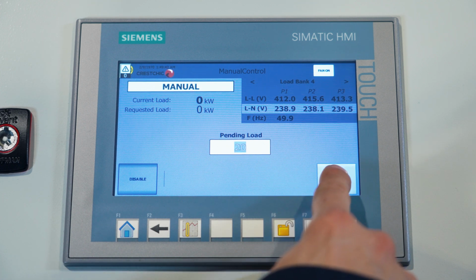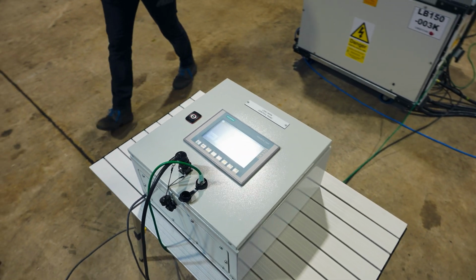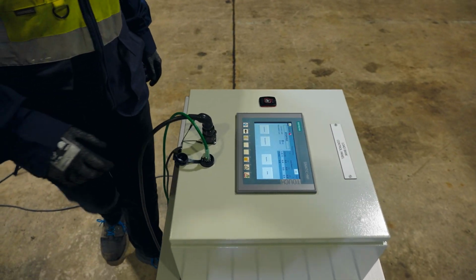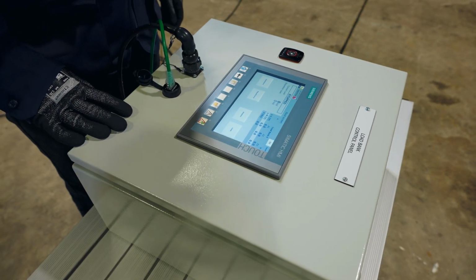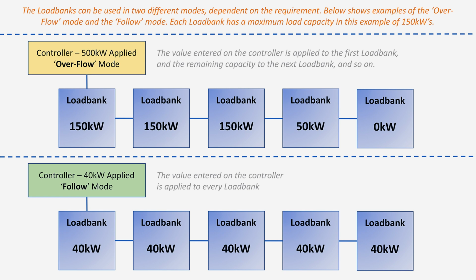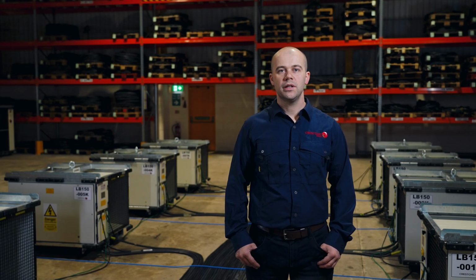Both three-phase and single-phase configurations are available for extra flexibility. The load banks can be controlled from one central controller, with instrumentation showing individual and total system load. And with two different modes available for load control operation, the load banks can either be loaded equally with the same load on each load bank, or to apply a total load with the first load bank capacity fully used, then the second taking up the rest of the load and so on. In short, these new load banks are very versatile for your data center testing needs.